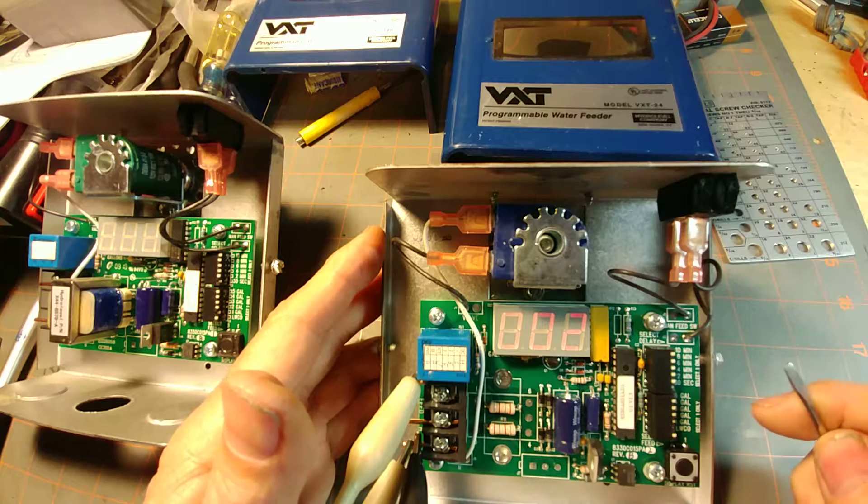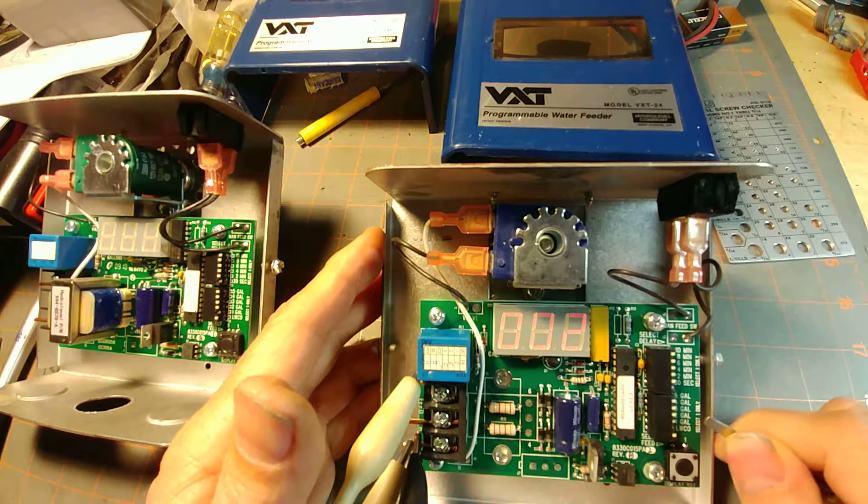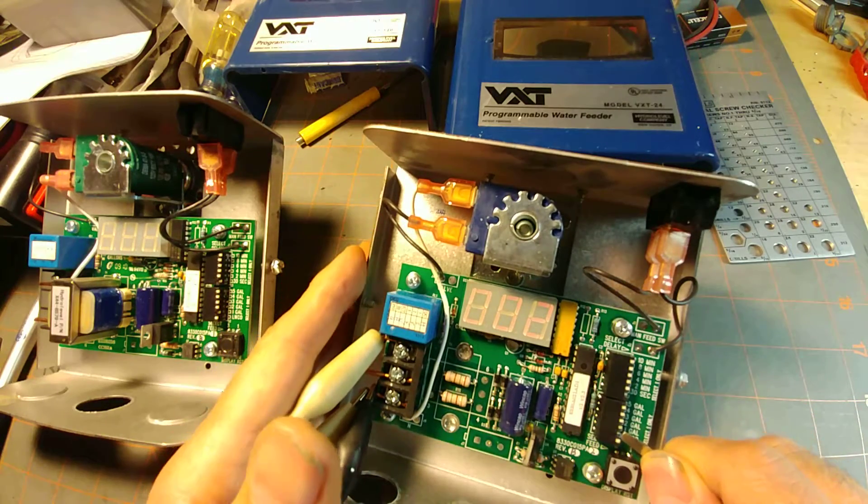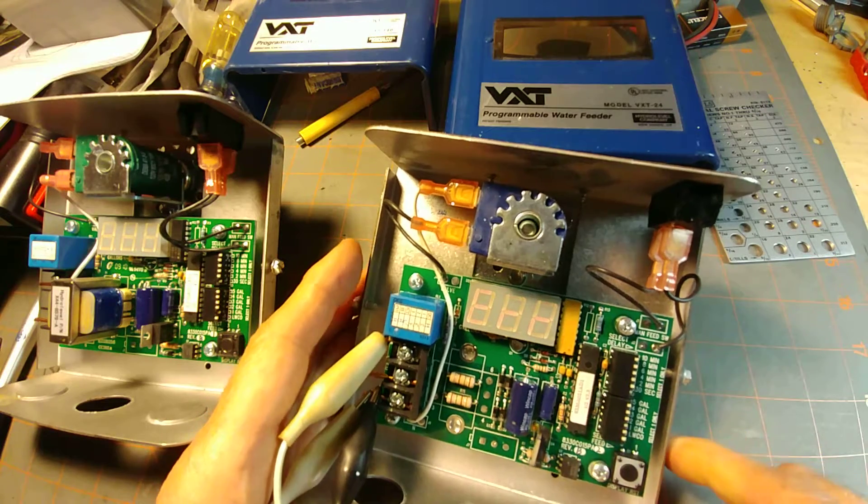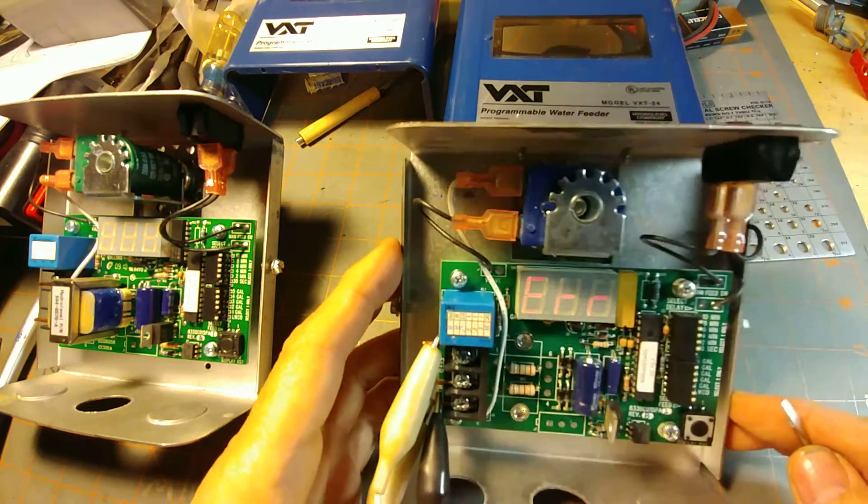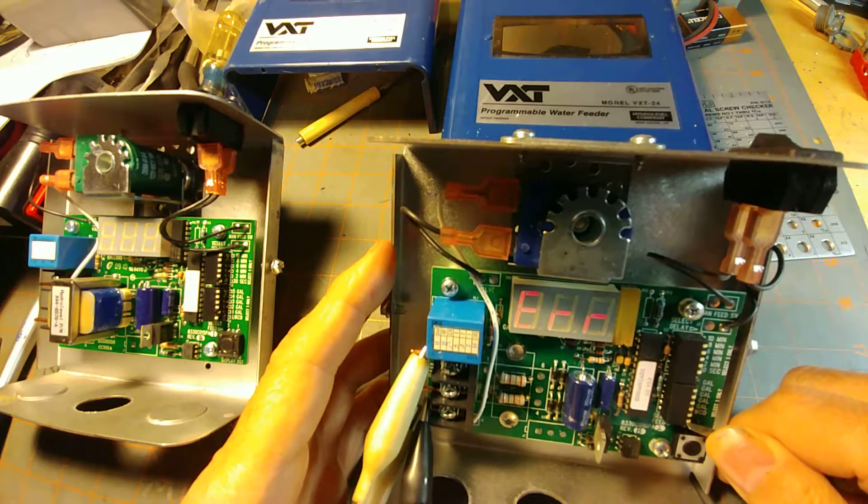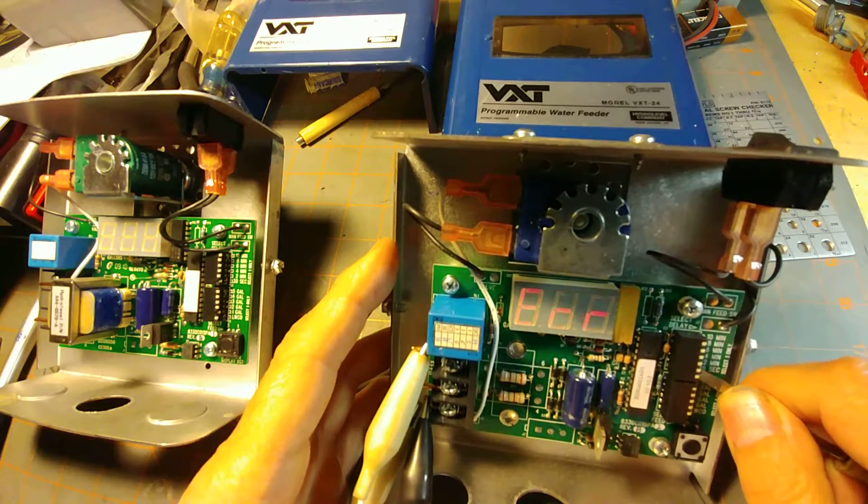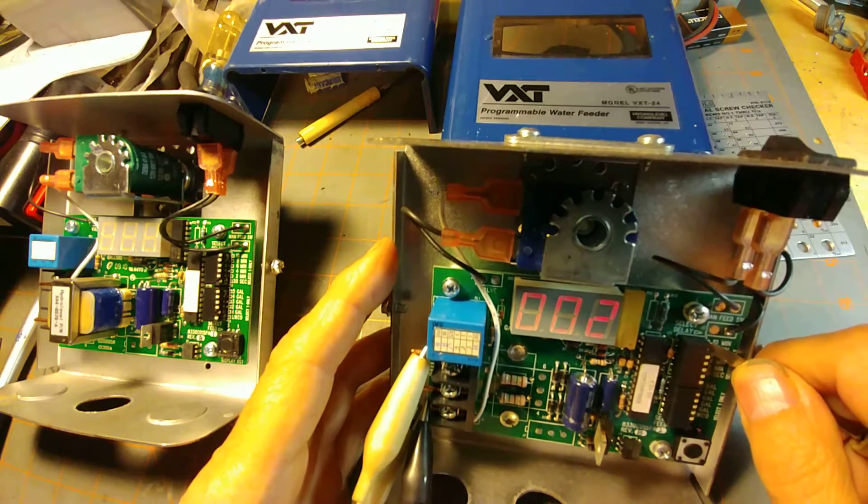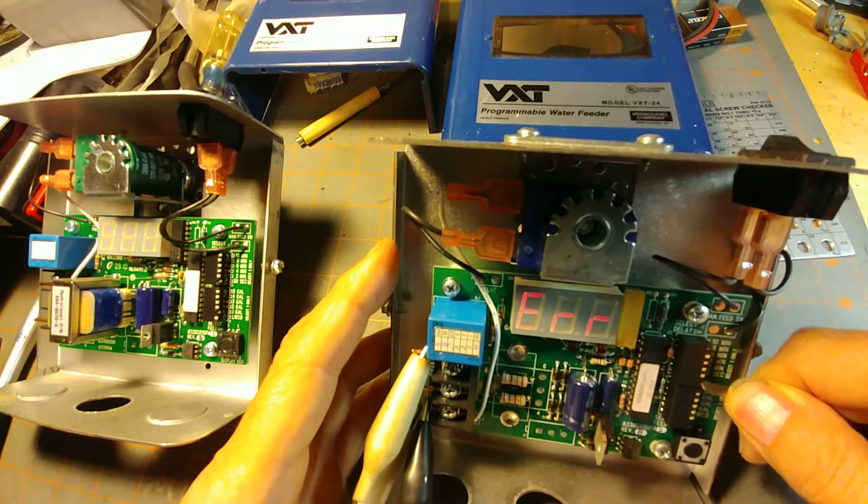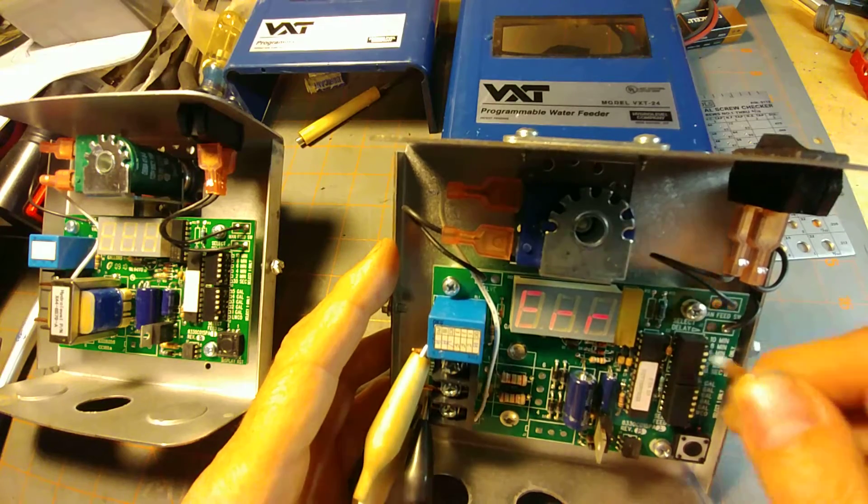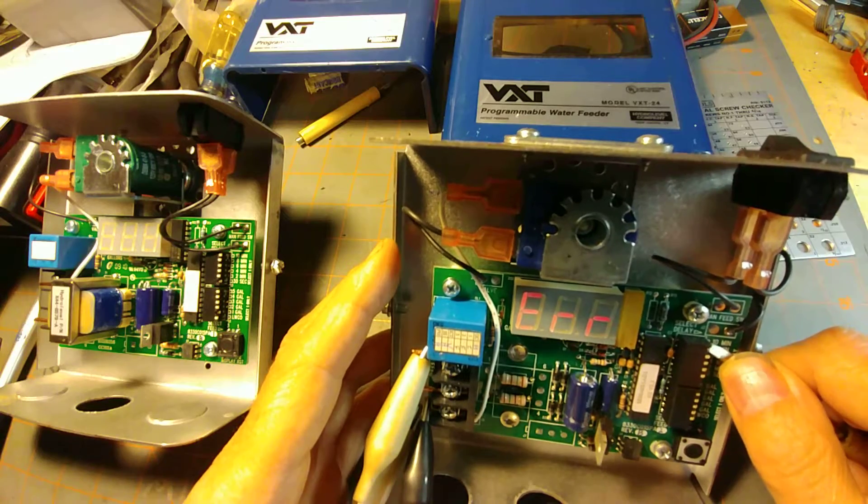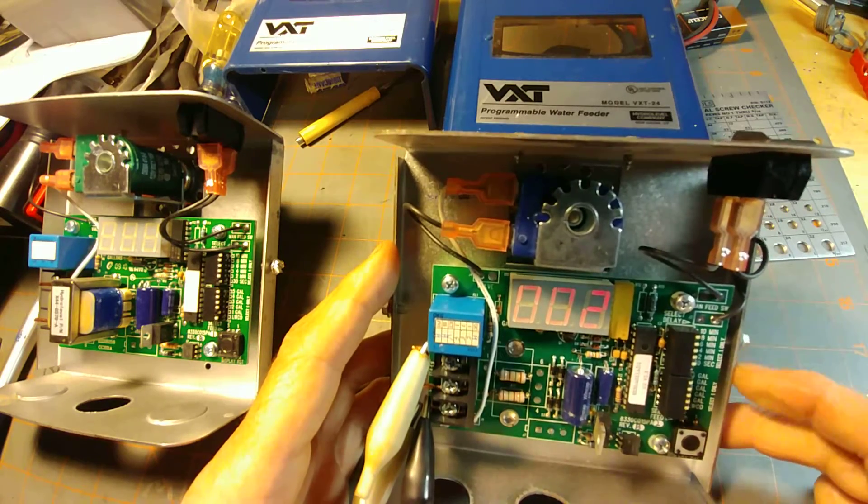Now, in order to set these DIP switches, usually you need like a point of a knife or a little tiny screwdriver. You set them like so, kind of reach in underneath the one where it's set and lift it up. If you don't reset it properly, it says error. You can set it to trip at low water cutoff. You can set the delay anywhere from 30 seconds to 10 minutes. But you've got to make sure that if you try to depress two switches at the same time, it'll read error. Or if you don't have anything set, it will read error. So we've got it set at 30 seconds and low water cutoff.